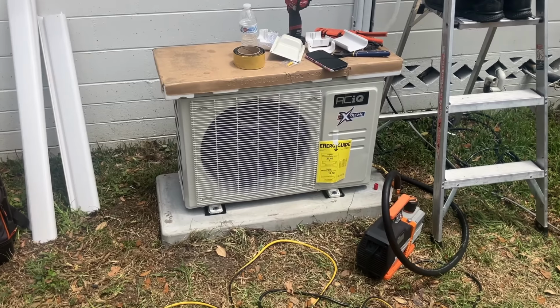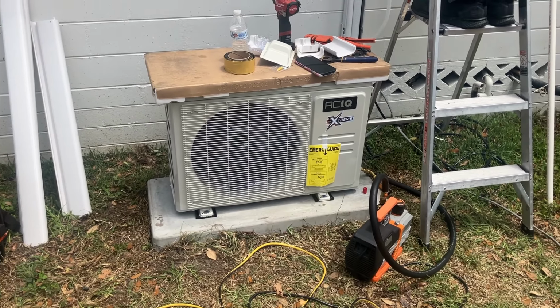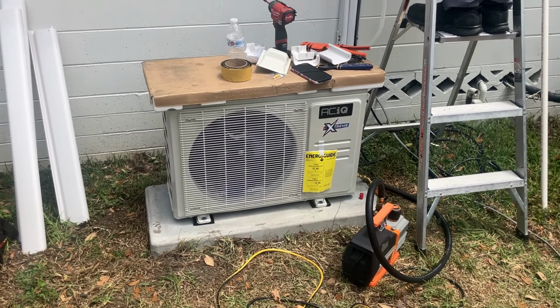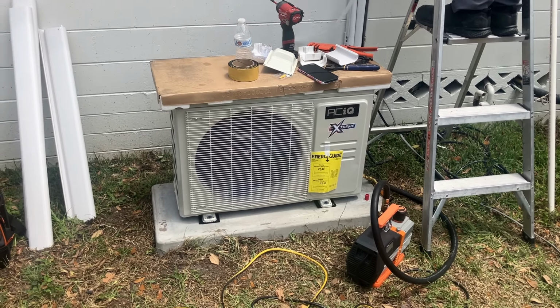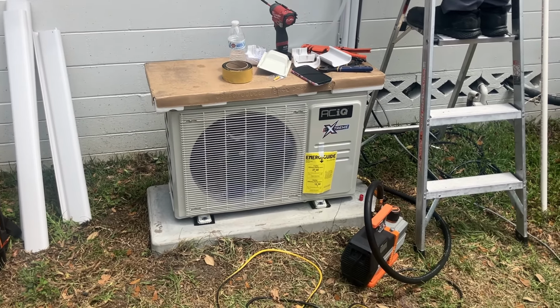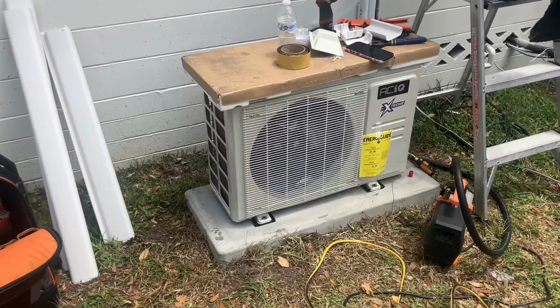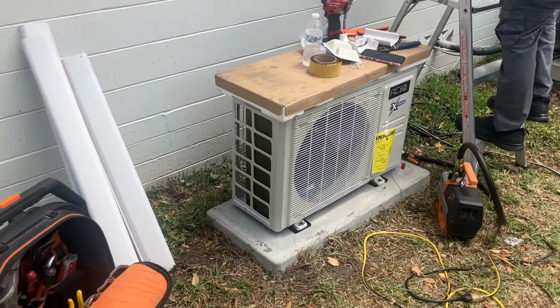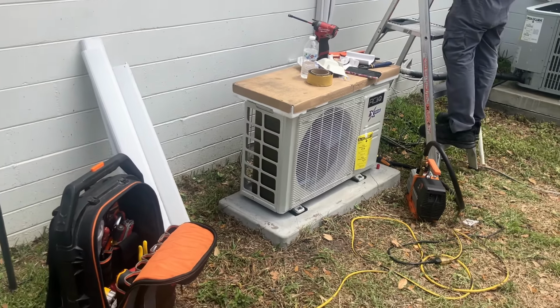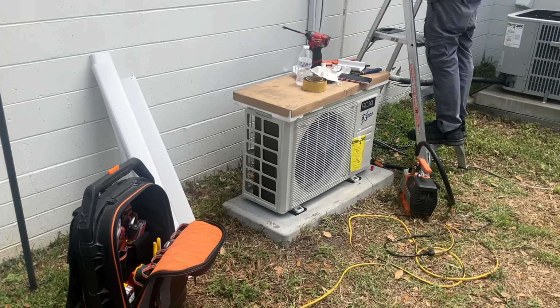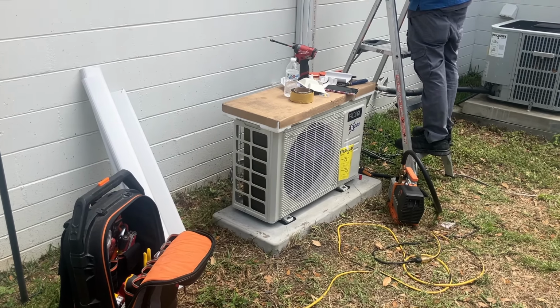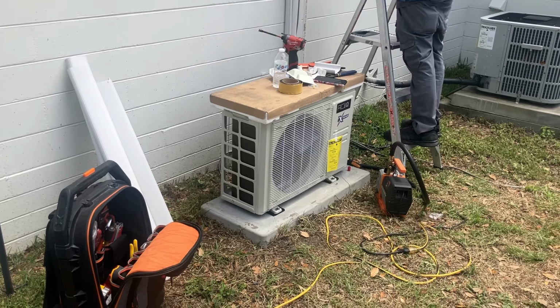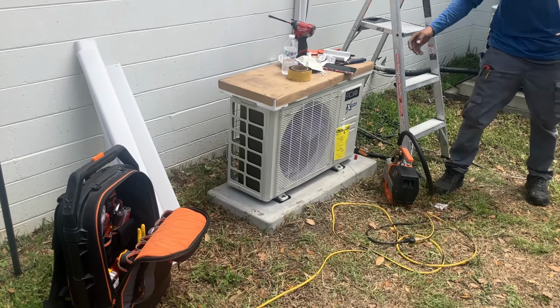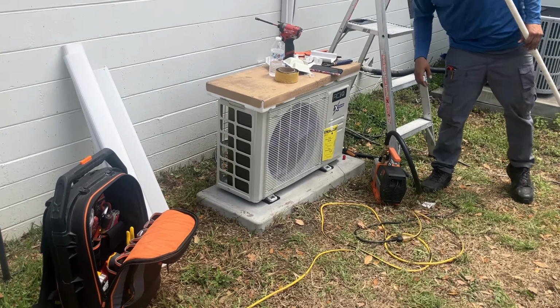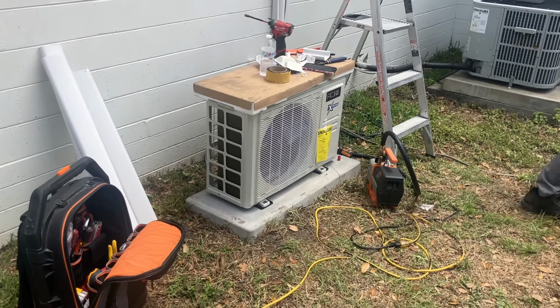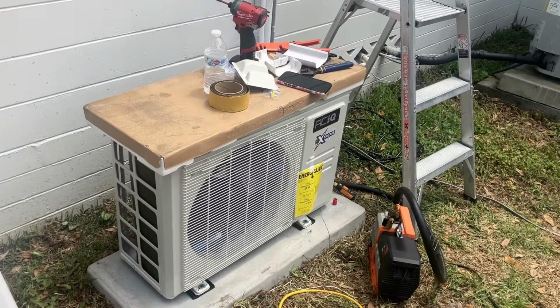And that's commissioning this beautiful ACiQ Extreme 9,000 BTU single zone heat pump system. Anybody can hang a unit on the wall, but this is where we make sure it actually performs well for many, many years. Right now we're pulling that vacuum, also duplicating a tightness test. We're going to do a decay test in just a few moments.